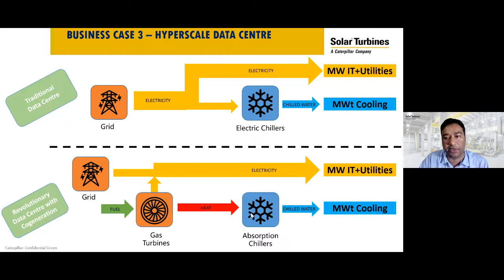Compared to that, if we go for a gas turbine, we can burn gas fuel or a different fuel like hydrogen, so in future we can use hydrogen fuel to completely decarbonize. With a gas turbine, we can generate part of the power requirement for a data center, with the other part coming from the grid. Then the gas turbine exhaust can be utilized in the absorption chiller, generating the chilling amount required for the data center.